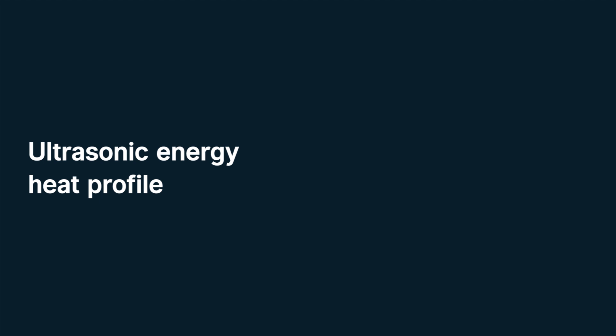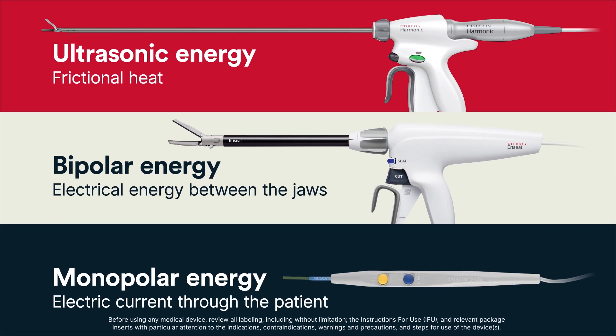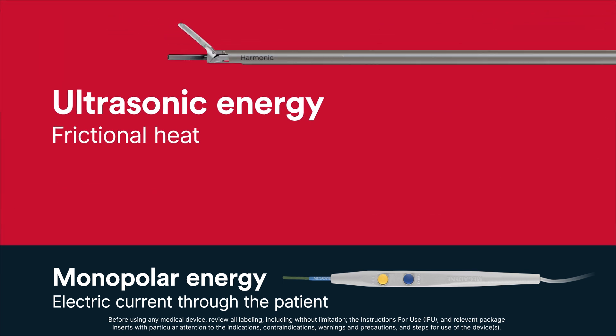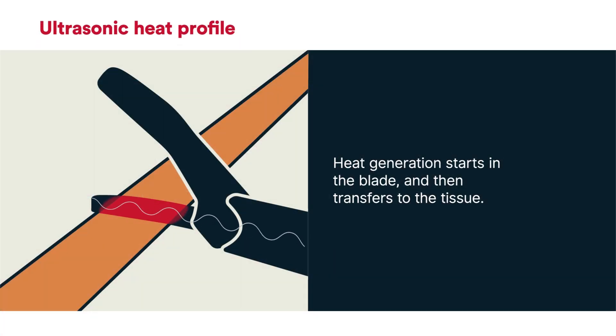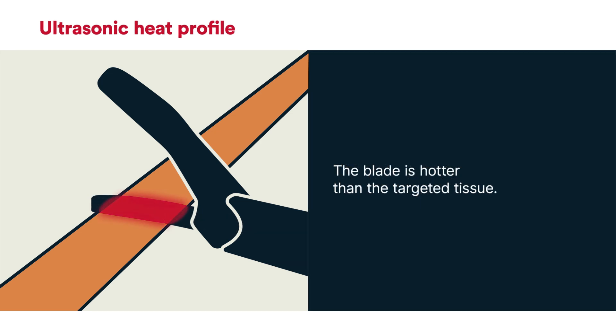Ultrasonic Energy Heat Profile. All energy devices intended to coagulate, cut, and seal vessels use heat. However, the effect of frictional heat on tissue is different than heat created from electricity, which bipolar and monopolar devices use, and are covered in separate videos. In ultrasonic vessel sealing, heat generation starts in the blade. As frictional heat builds in the blade, the heat transfers to the targeted tissue. If one were to measure the temperatures at the end of the sealing cycle, they would find the blade is hotter than the tissue.